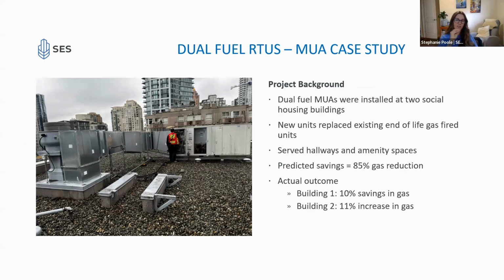People are putting these in and they're seeing... well, I'll just give you an example here. This was one case study. It's actually written about in the electrification guide in more detail. This was a social housing building, so it is makeup air, not a rooftop unit, but the commissioning and considerations associated with a makeup air unit and a rooftop unit are going to be very, very similar. So I'm talking about this case study just because it's got some good data right now. Next time we talk about this, I'll have a bunch more rooftop unit ones, but the learnings are going to transfer, which is why it's important to talk about it.